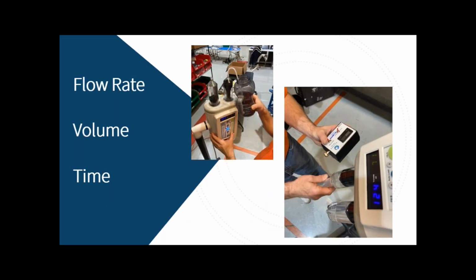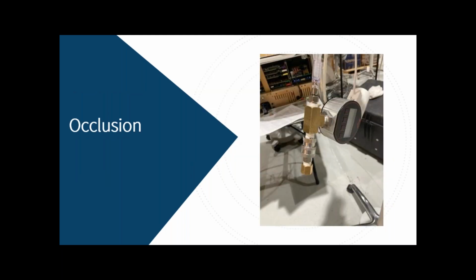So flow rate, volume, time. All this looks familiar, right? You fill up the syringes, graduated cylinder, you fill up the IV bag, you send it to the infusion pump, you go into a graduated cylinder, you see how much you have. Anything different on that? Nope, nothing's different. And you have a stopwatch or something to time it, correct? Nothing's different. Occlusion. You block off your infusion pump, right? And it's supposed to occlude at a certain pressure at a certain time, right? Same type of deal here. There's an occlusion and there's a pressure gauge to see what it occludes at.